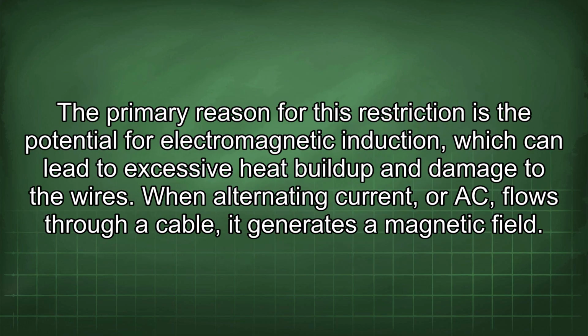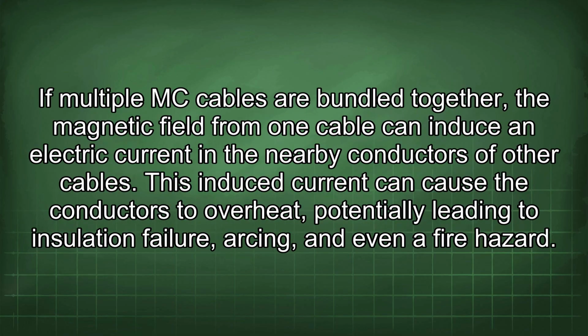The primary reason for this restriction is the potential for electromagnetic induction, which can lead to excessive heat buildup and damage to the wires. When alternating current, or AC, flows through a cable, it generates a magnetic field. If multiple MC cables are bundled together, the magnetic field from one cable can induce an electric current in the nearby conductors of other cables. This induced current can cause the conductors to overheat, potentially leading to insulation failure, arcing, and even a fire hazard.